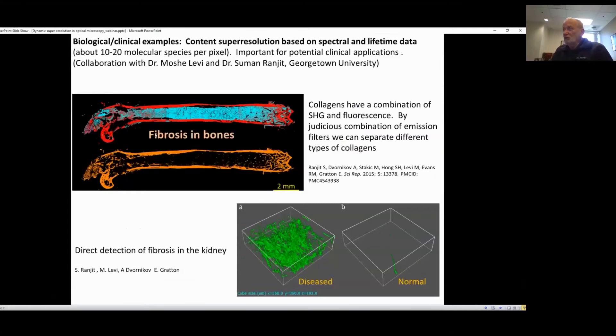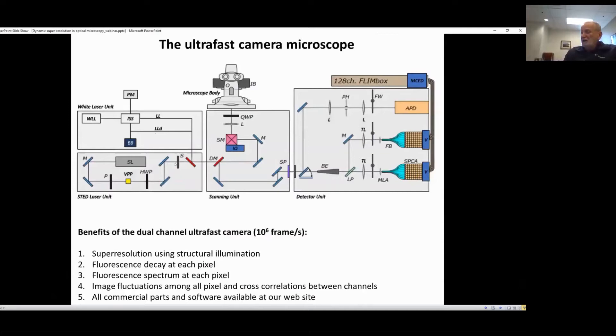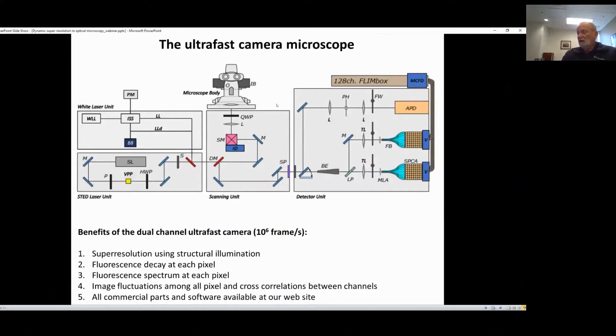The advantage of this setup is that we can obtain a very large number of frames per second, because you can read every element of this detector in a microsecond. Everything in parallel goes to what we call the FLIMbox, and we can obtain all the information — fluctuation, lifetime, spectrum, and so on — directly, at very high speed. Every pixel of this camera is measured separately and independently. We can obtain the fluorescence decay at every pixel, the fluorescence spectrum at every pixel, and fluctuation among all the pixels, giving us an idea of where the molecules move.